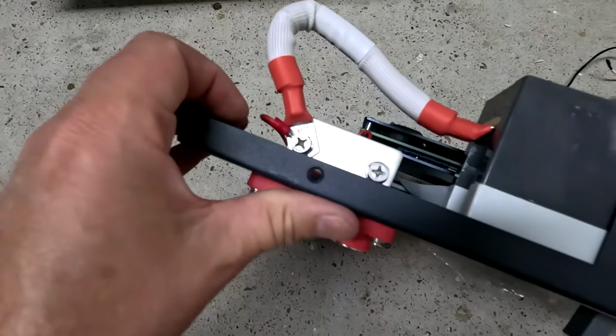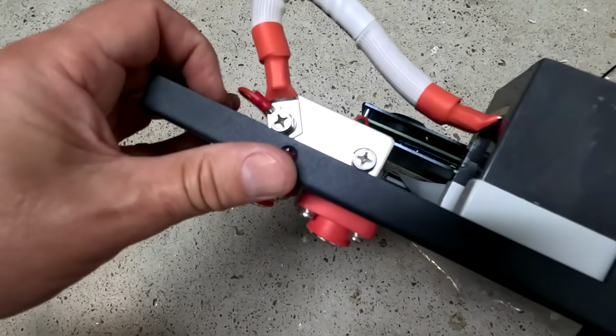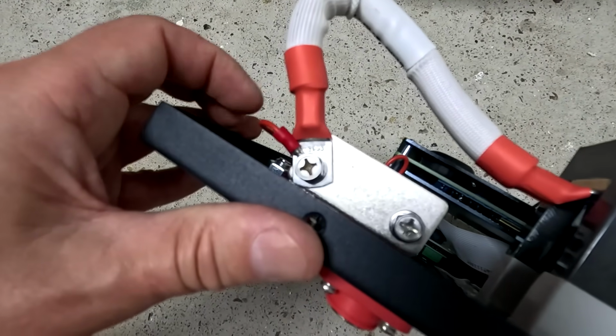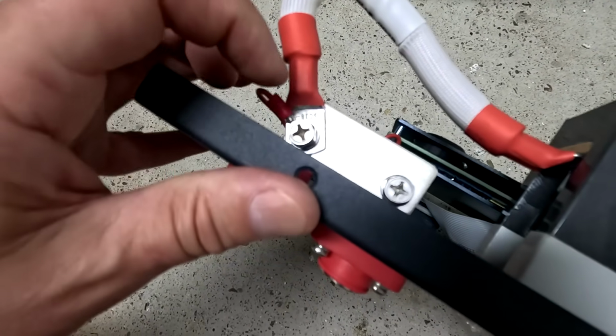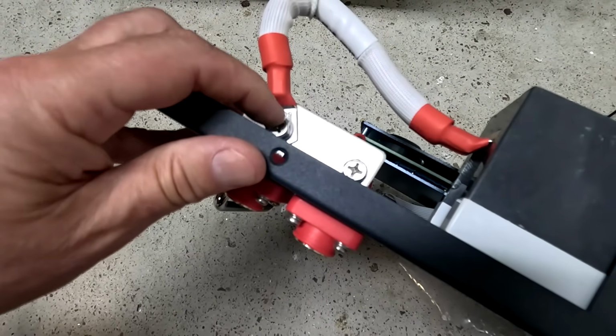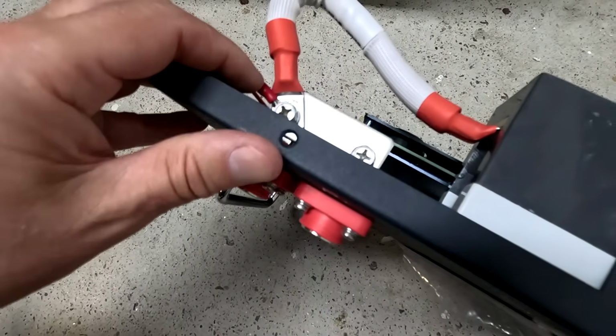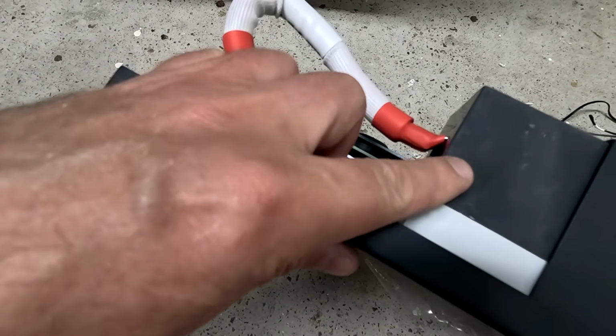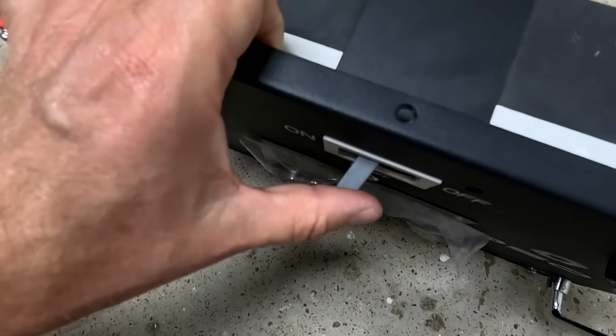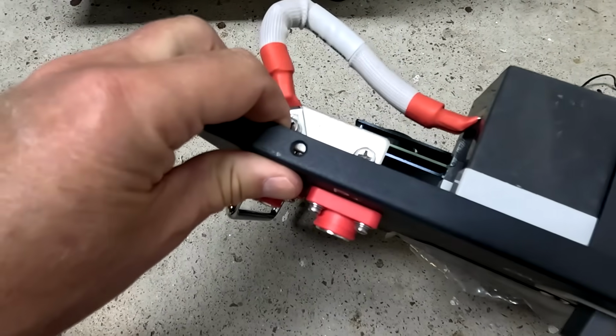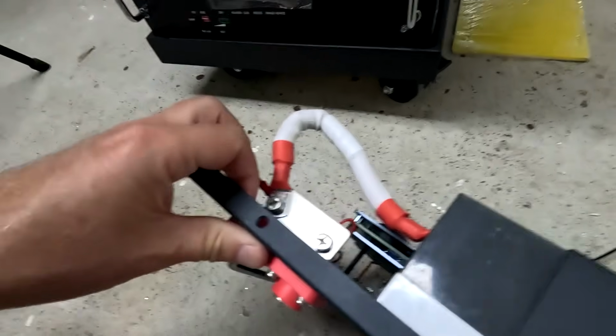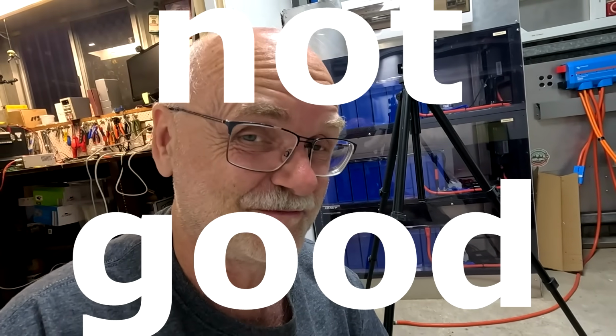And then here we've got something very unusual. This is the positive power supply connection to the BMS, and it is connected to the main positive terminal of the box, but it is after the circuit breaker. So when you turn off the circuit breaker, the BMS will turn off as well. And this is not good design, because if the circuit breaker trips or you turn it off, you still want to have access to the BMS.